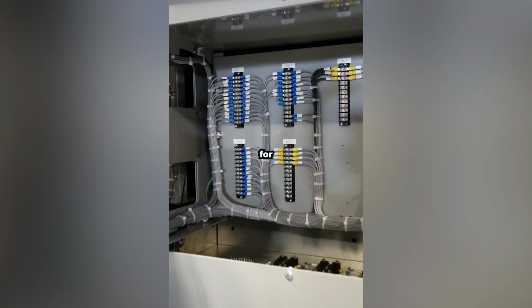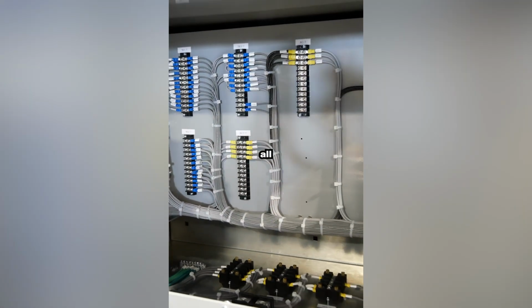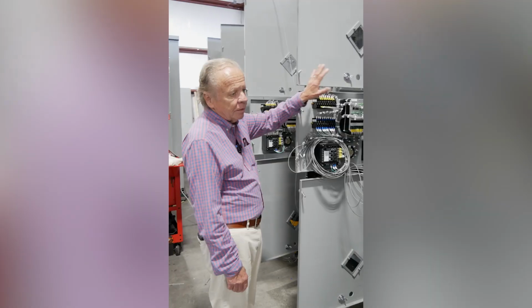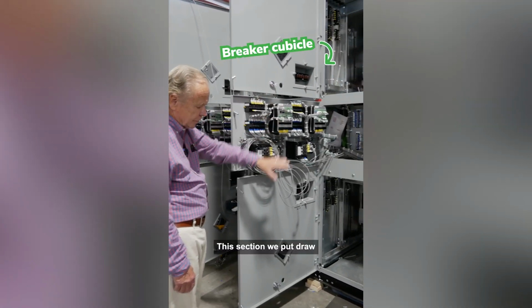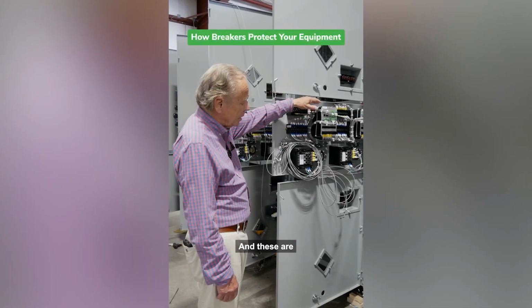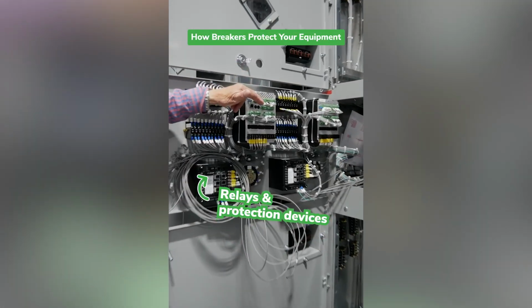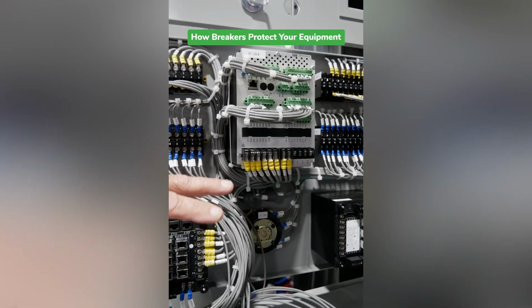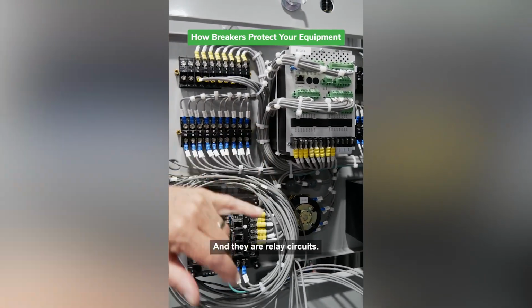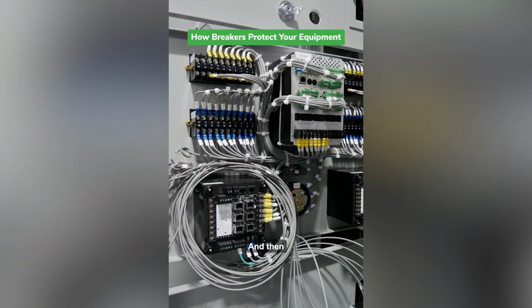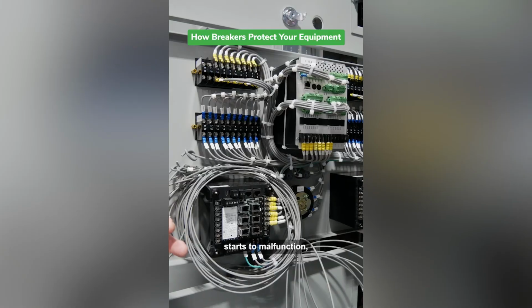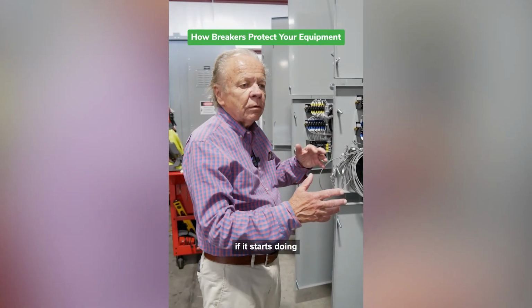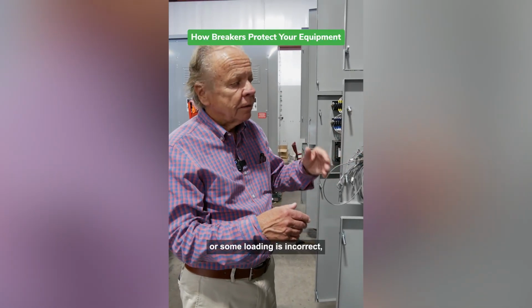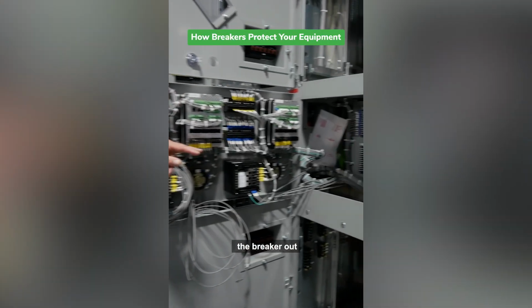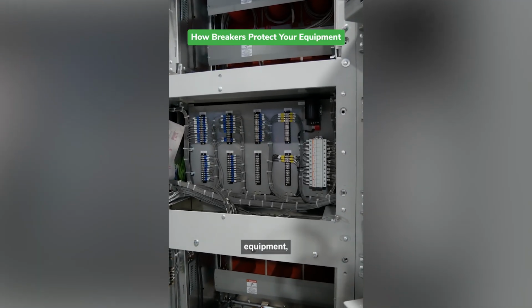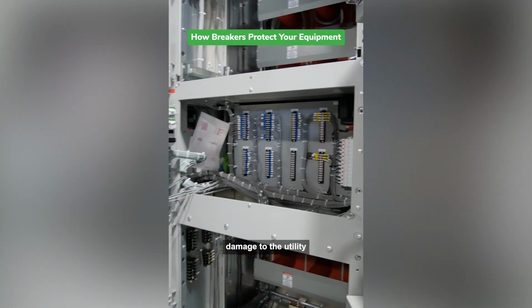Inside, you've got a lot of wiring for relays, control switches, and terminals, and all of this is for the breaker. This is a breaker cubicle right here. This section we put draw-out breakers in, and these are relays and protection devices that protect the breaker. They are relay circuits. Some of them are as simple as controls to fuses, and if the breaker starts to malfunction, starts doing something wrong, or some loading is incorrect, these devices trip the breaker out so it doesn't cause any damage to the customer's equipment, or, more importantly, cause damage to the utility company upstream.